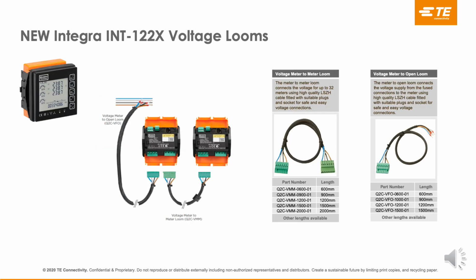As we mentioned on the previous slide, the products do have voltage in and voltage out connectors. To make it easier for installation, we can also provide looms to satisfy the daisy chain needs. So we've got a Q2C VFO loom, which is basically the fuse to the voltage in to the first meter, and then we have a Q2C VMM, which is a voltage meter to meter loom that can then daisy chain the voltage down the panel for the outgoing ways of each meter. Different lengths, as you can see, 600mm up to 2 meters is our stocking policy. We can make different looms to length if needed, but we feel they're the commonest loom lengths that are required.